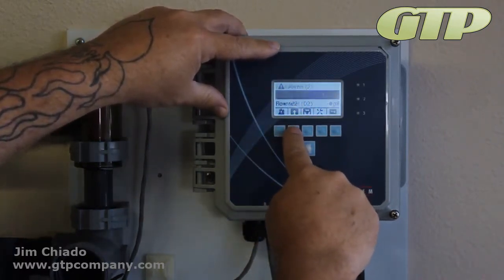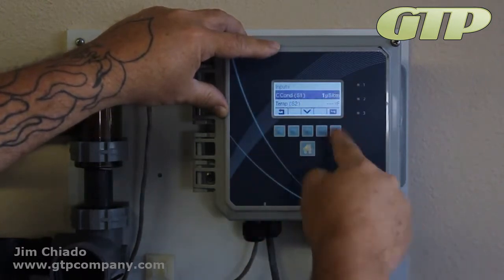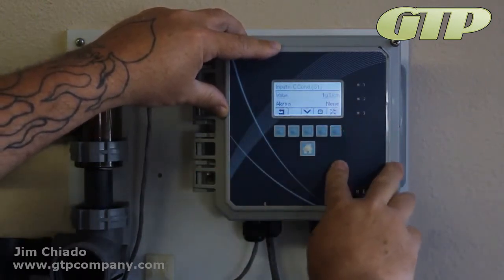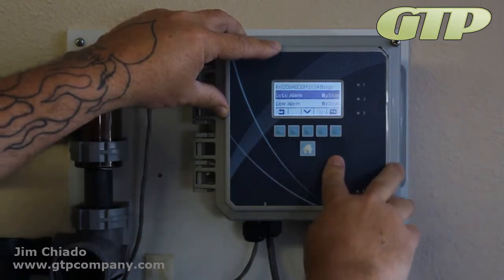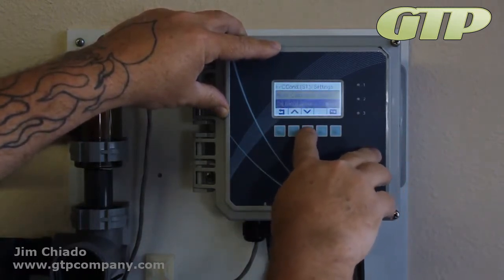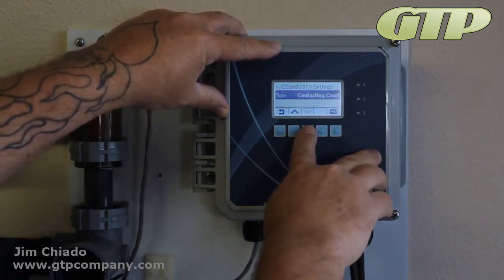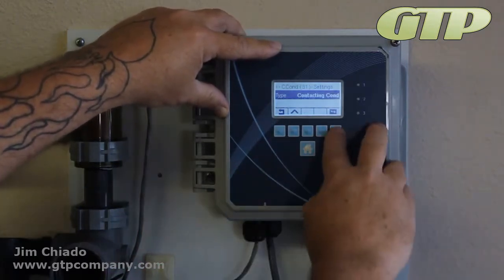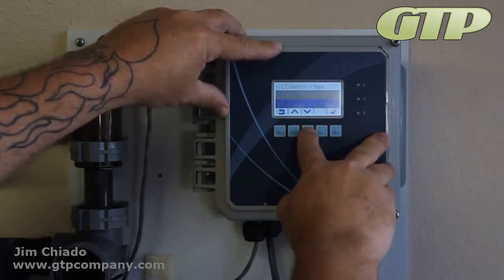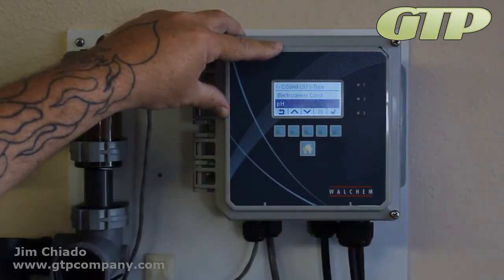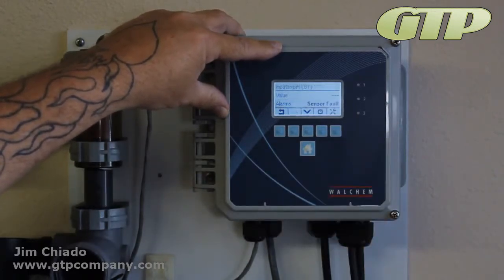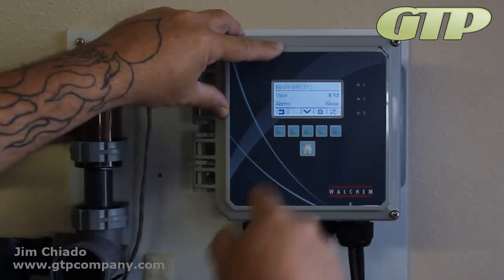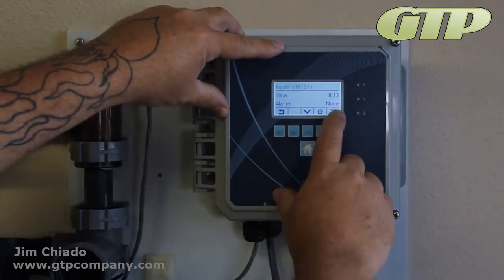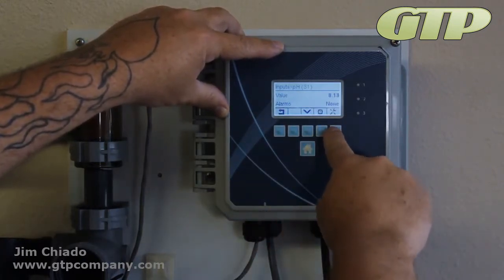So inputs, right now it's on the CCond, but we know we've added the pH, so we're going to hit that. Maintenance, and go to the bottom. You want to go first and change the type so that we're already looking at the thing. Pan down to where it says pH, click check. Everything's going to change a little bit, and we should get a value because we've wired it. We've done everything that we needed to here. There, 8.12.